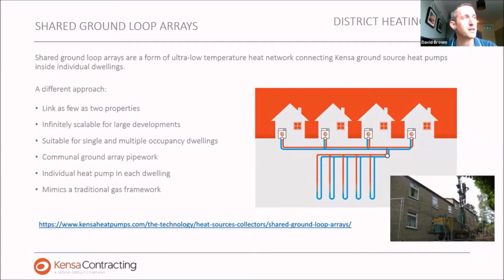This circuit will typically operate anywhere from 2 to 6 degrees, but in certain applications can run as high as 10 to 15 degrees through that ground array circuit. But because we're operating at ambient temperature, as we flow through the ground between multiple buildings, or if we flow through a riser in a high-rise block, for example, we remove all of the system distribution losses from the system. So straight away, all of that extra running cost compared to a district heating system is removed.